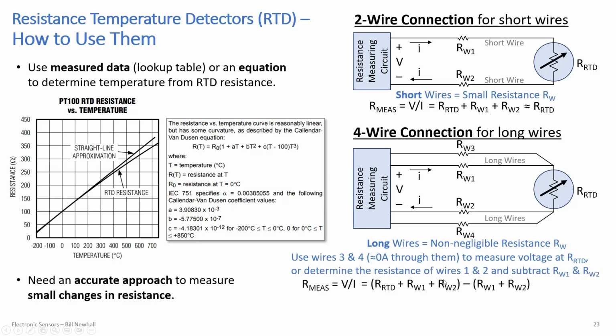You could do this a couple of ways: measure the voltage and current back at the instrument, or figure out the actual resistance of wire 1 and wire 2 based on your known current and known voltages across those pairs. So that's the 4-wire connection.